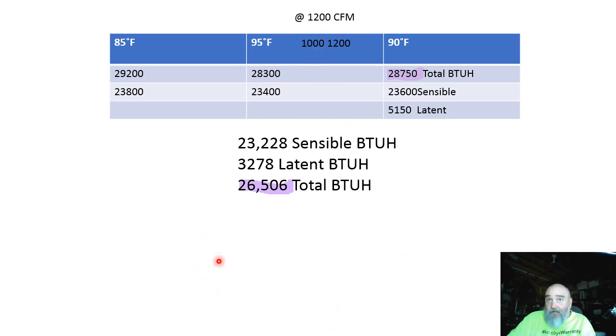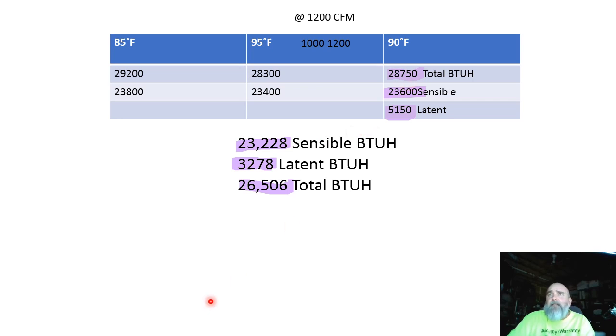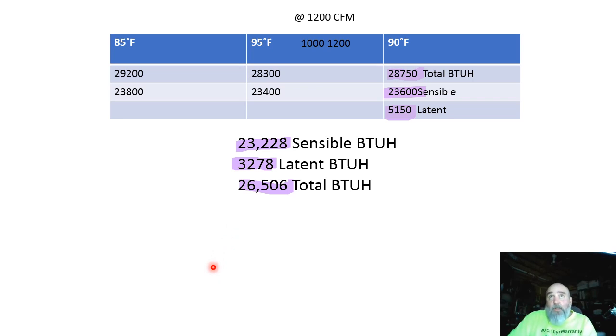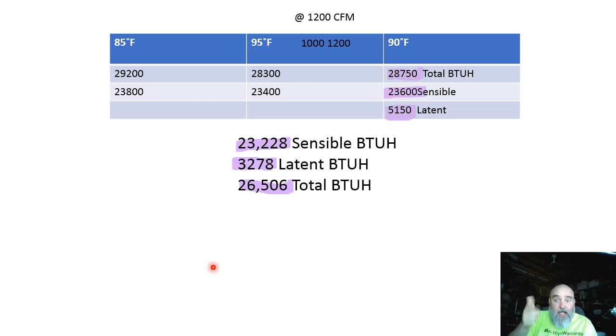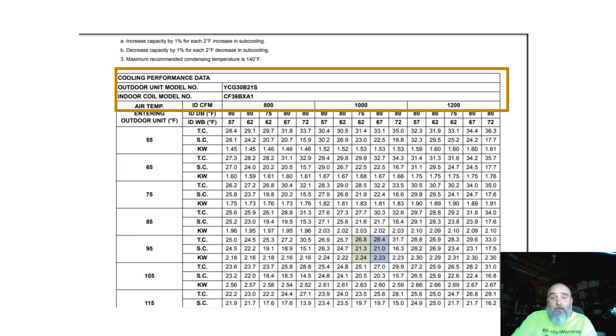At 1200 CFM on this two-and-a-half ton piece of equipment, we're covered on total, sensible, and latent — everything checks out. When was the last time you thought you'd hear 1200 CFM for two and a half tons? 400 CFM per ton — the 'beer can cold' method — is not how you charge equipment and it's not how you select equipment.